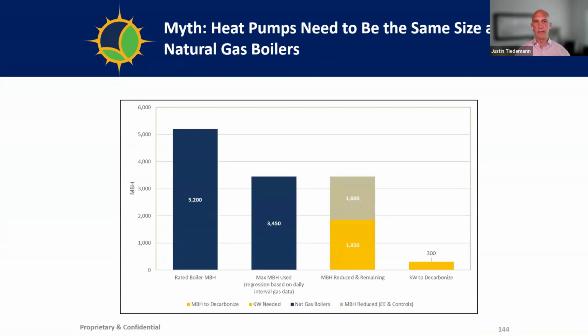And then another myth is, we have this size of natural gas boiler, so we need to put in the same size heat pump technology or electric boilers, whatever it might be. Again, you have to look at the 10 years of data, at least 1 year. The more, the better. And in this case, you can see that the actual heat load on the building was significantly less than what the boilers were sized for. Then looking at efficiency, this would be the third bar. You're taking out the heat load with efficiency, and whatever's left over is what you have to decarbonize. And it's not as much as you might think. Last slide.